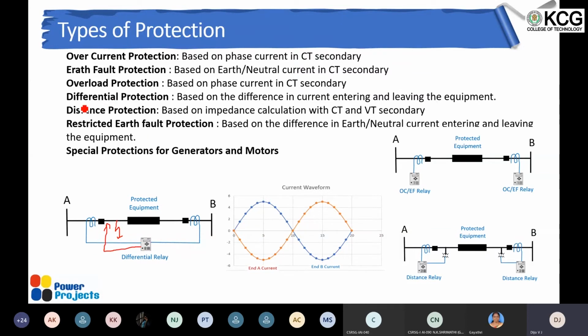Now, differential protection. I think this is important, because when we talked about the zones of protection, in order to ensure that the relay operates only on its zone, we need to understand a little about differential protection, so I'll explain it briefly. It's here. You can see two CTs connected to the same relay. The relay gets information on the current flowing through one end and the current flowing through the other end.